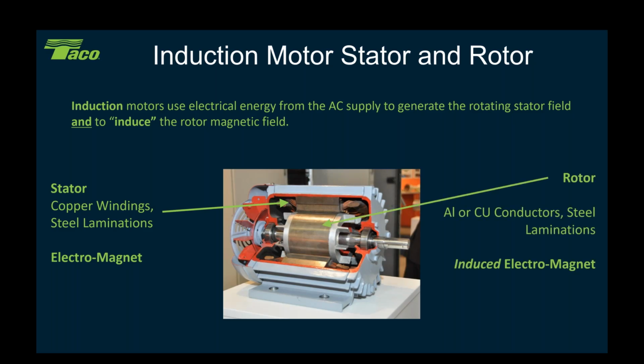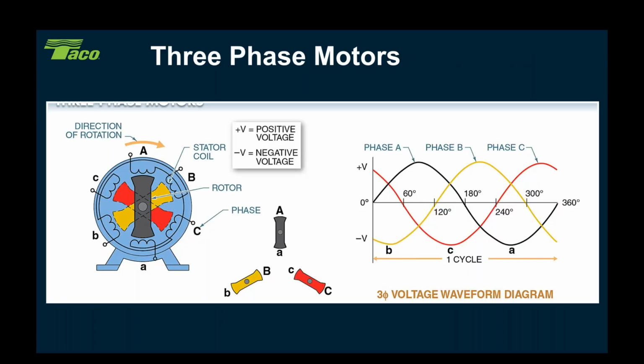And then we have the rotor, and again, that is steel and copper, and we induce a voltage or a current in that rotor to create the magnetic field, because there are no actual electrical connections between the power source and the rotor. It is all induced current. So we look at a typical three-phase motor. We have three phases in the rotor and three phases in the stator. The two rotating fields are slightly out of sync from one another, and the rotor is constantly chasing the magnetic field in the stator. Magnets oppose, like north and south and all that. You're creating the magnetic field, and so it's causing that rotor to constantly move because it's trying to chase that magnetic field in the stator. It continuously moves, and that's what causes the rotation within the motor.